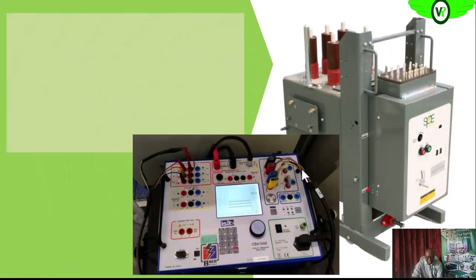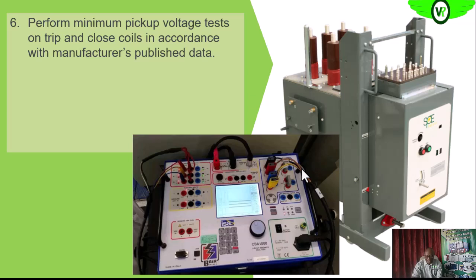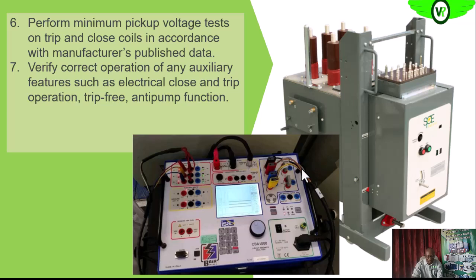in accordance with that standard. So the other test that we want to do using the circuit breaker analyzer is the minimum pickup voltage. Okay, and we are going to do that on the trip coil and the closing coil, the minimum voltage that the coil will actually be energized. Okay, so we are going to check for that. Then we also want to verify that all the auxiliary features, okay, such as the close and the tripping features of the circuit breaker associated with the circuit breaker, is operating properly.